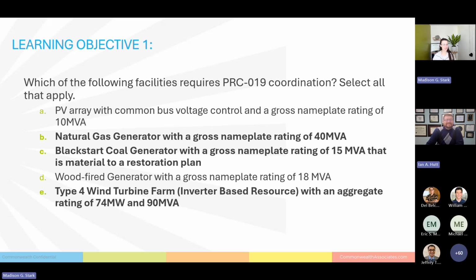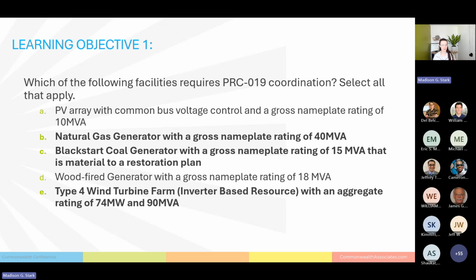So these three are of the 5 selections that apply. The PV array and the wood fire generator are both under that 20 MVA capacity, so they don't apply. And I'm glad that everybody got C as well, which was a little bit of a trick. It's that black start, which is very important to include in the PRC 19.